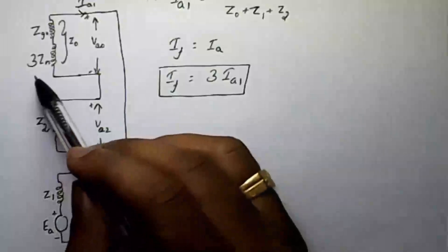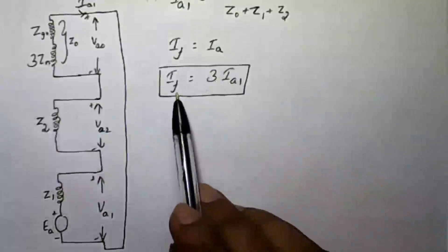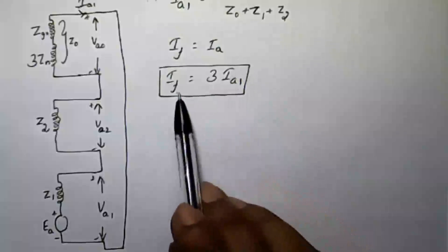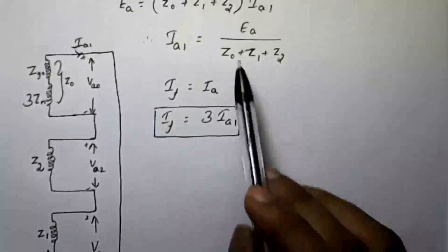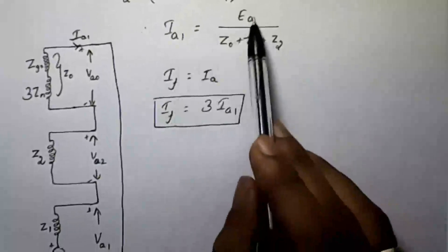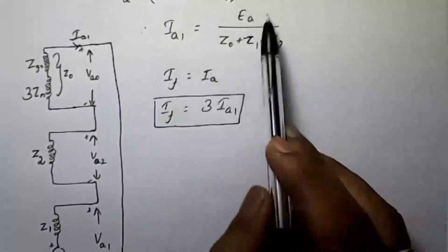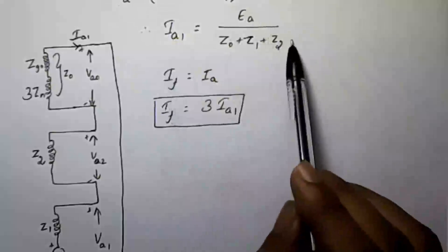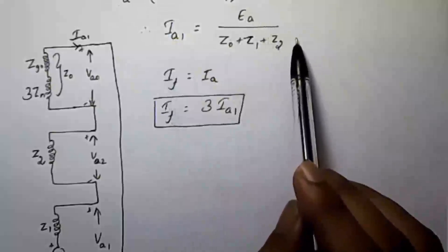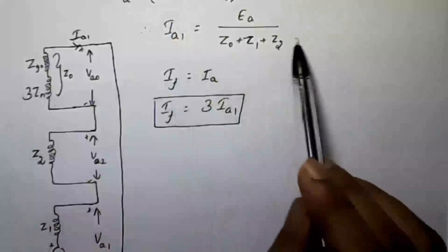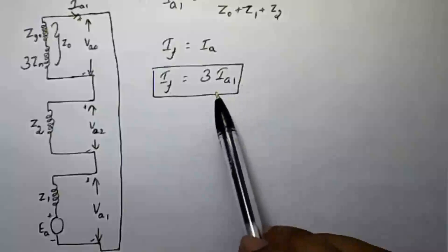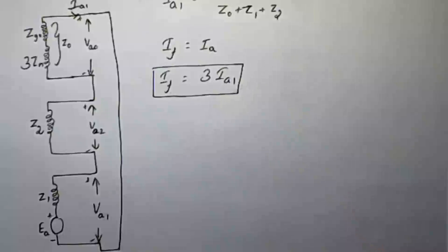This sequence network is also important. The fault current can be easily calculated using IF = 3×Ia1. If any one sequence current value is known, multiply it by 3 to get the fault current. Alternatively, if the sequence impedance values are given, use Ia1 = Ea / (Z0 + Z1 + Z2), where Ea is the pre-fault voltage, normally taken as 1 per unit. If a neutral impedance Zn is given, add 3×Zn to the zero sequence impedance. Thank you.